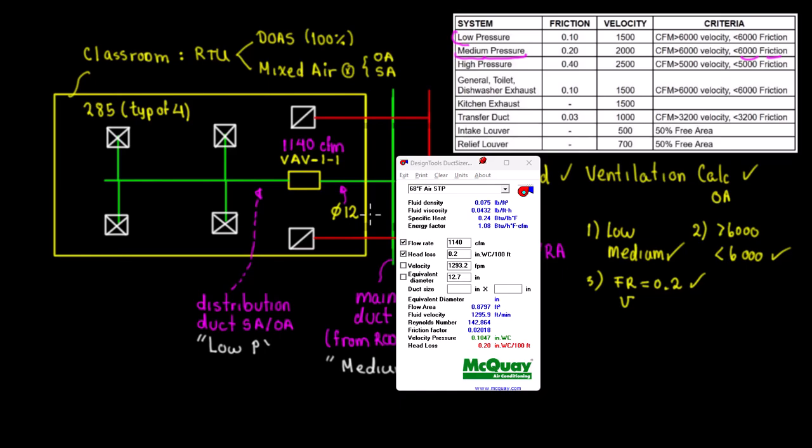But this has to go with the manufacturer. You don't need to do this sizing calculation, because these VAV boxes already come in nominal sizes like 8, 10, 12, 14 based on your CFM maximum and your CFM minimum. Contact the rep. They have their own procedures, they have their own team, and then you will get the appropriate number. But this is an example. Now what we're going to do, which is more practical for this video, and I'm sorry I'm extending the video a little bit more, is the downstream. So let's continue with that part.